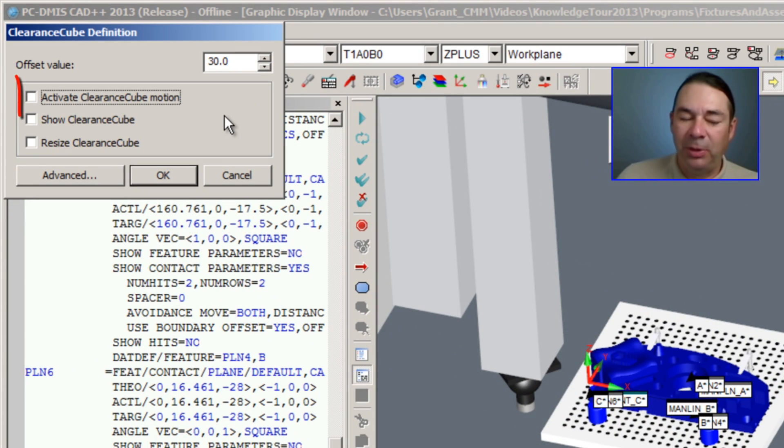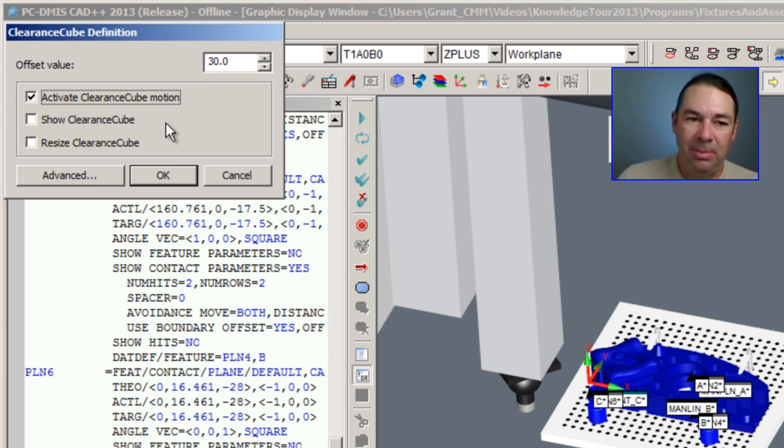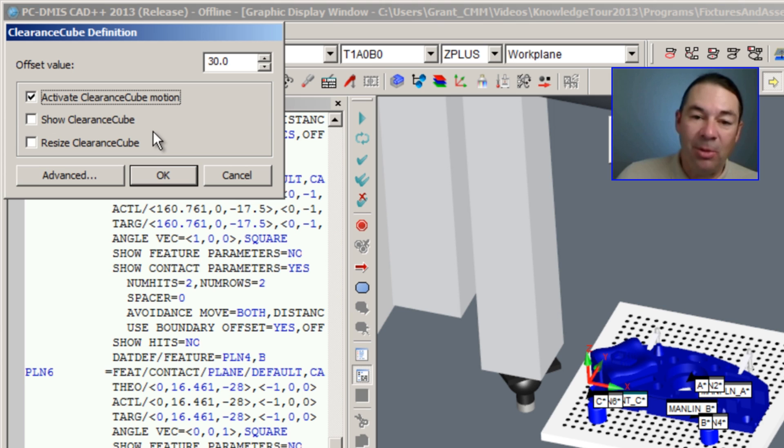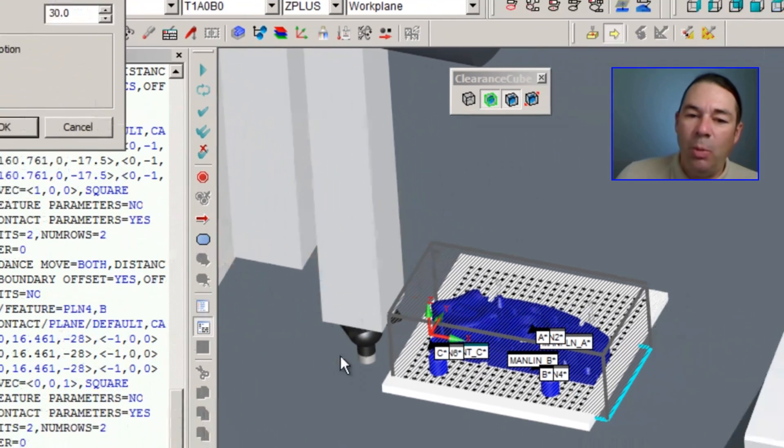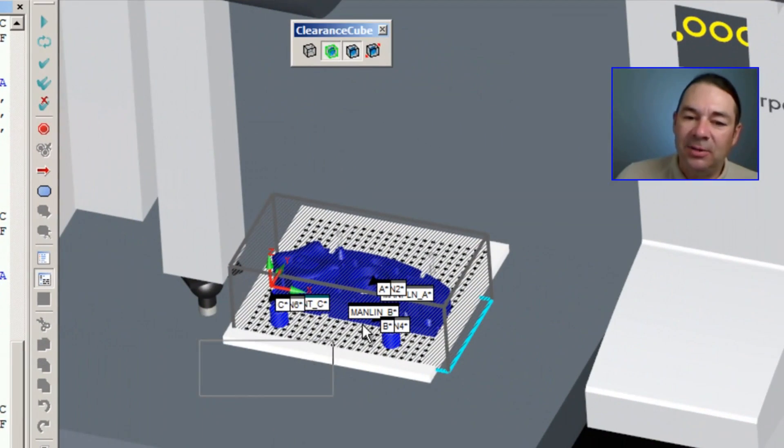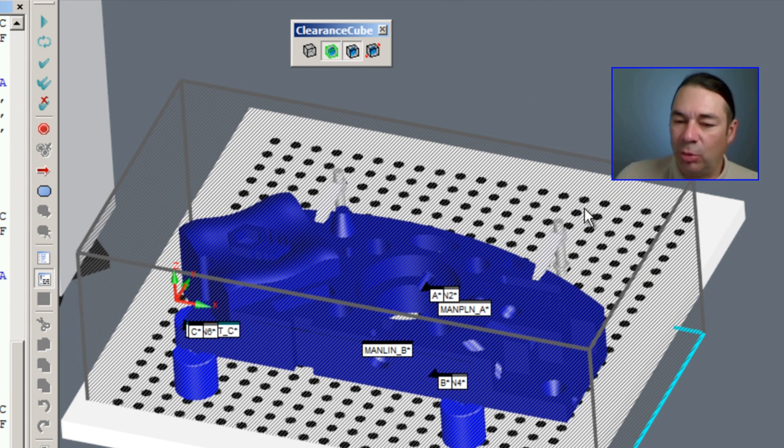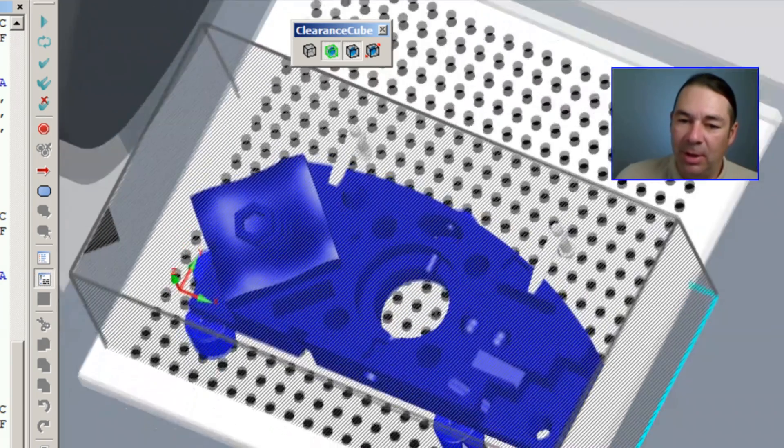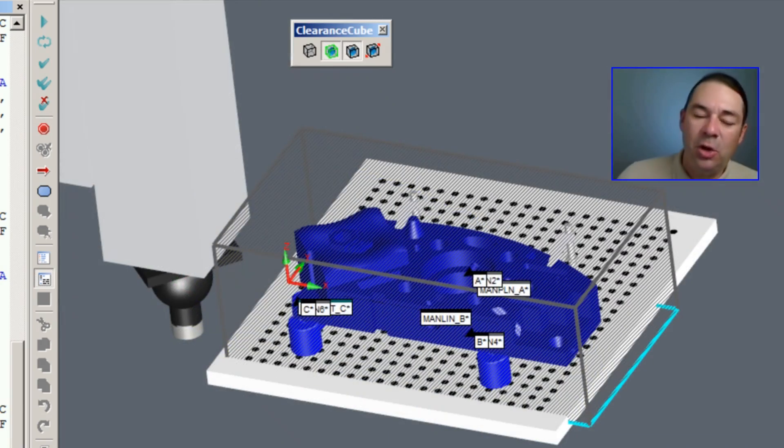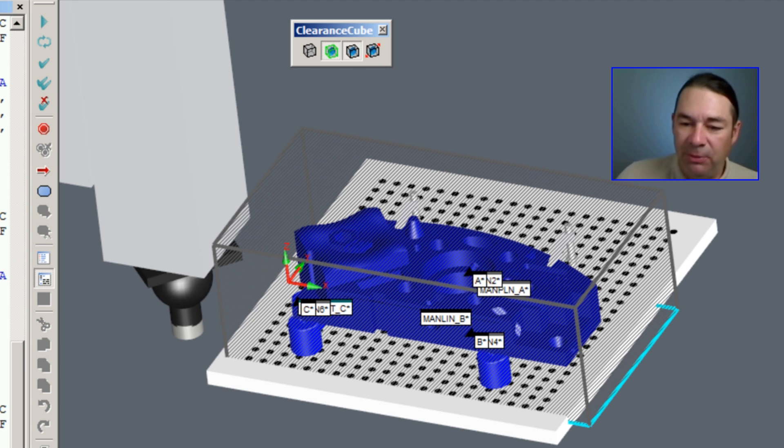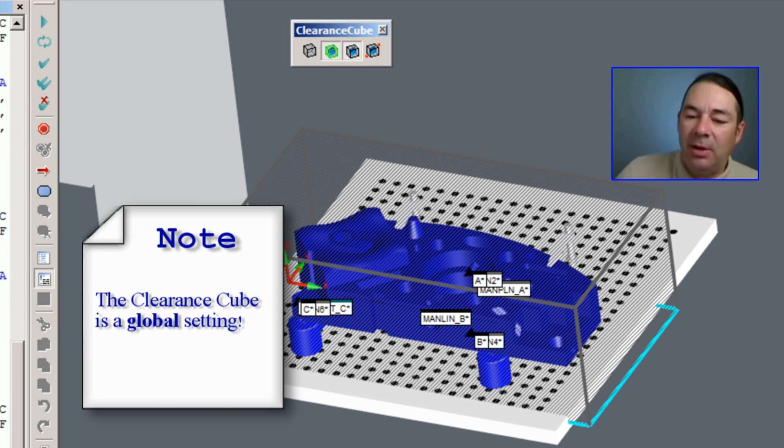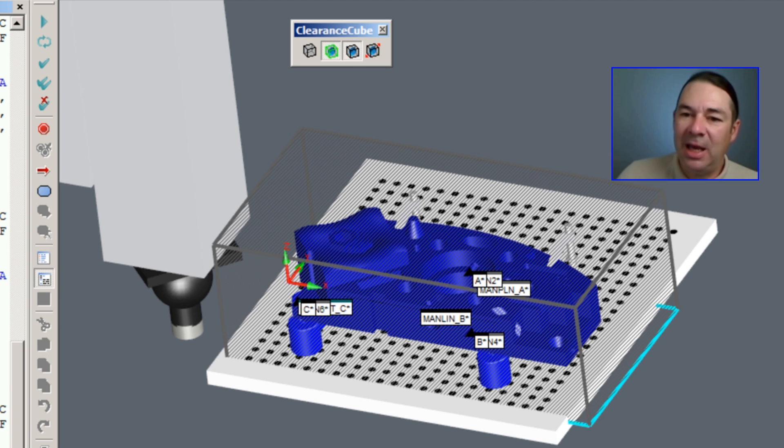The next thing that I'm going to do is place a check next to the option activate clearance cube motion. The third thing I'm going to do is display the clearance cube, and we can see inside the graphics display window PC-DMIS draws a cube around our part. This cube represents the safety zone the probe will drive to before measuring any features. This is a global switch, and when we turn this on, PC-DMIS is going to take any new measured features and automatically apply the clearance cube command to it.